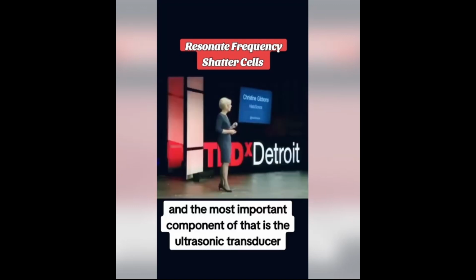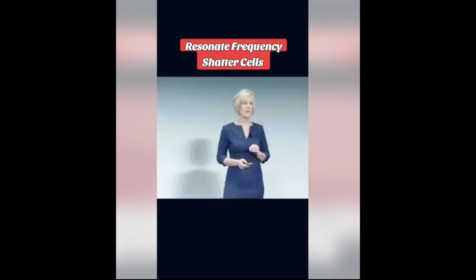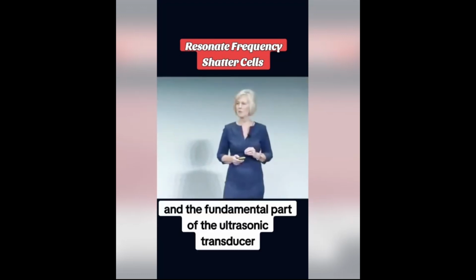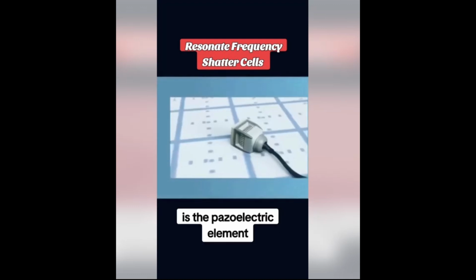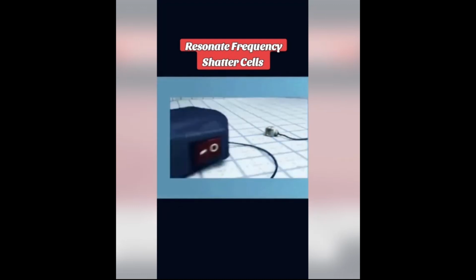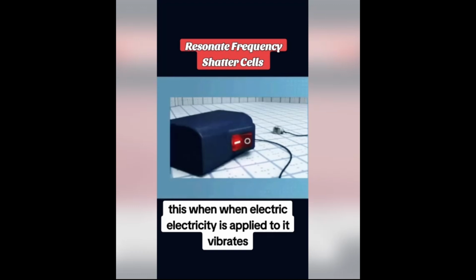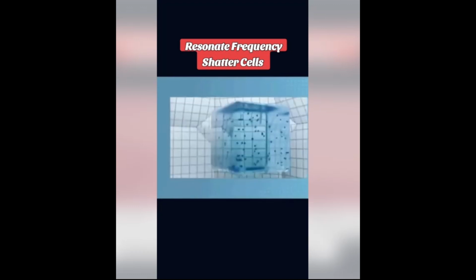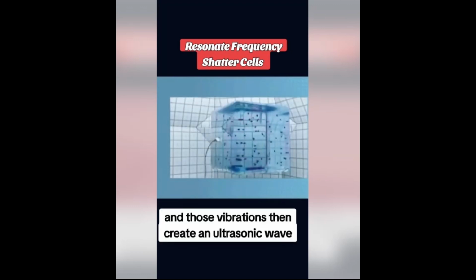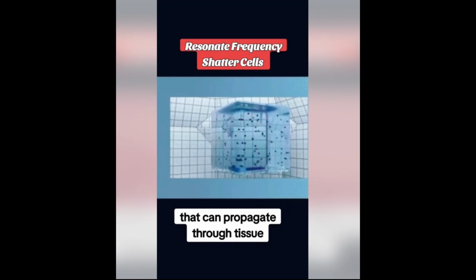And the most important component of that is the ultrasonic transducer. And the fundamental part of the ultrasonic transducer is the piezoelectric element. This, when electricity is applied to it, vibrates. And those vibrations then create an ultrasonic wave that can propagate through tissue.